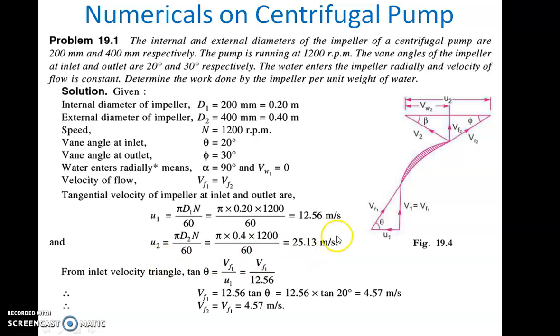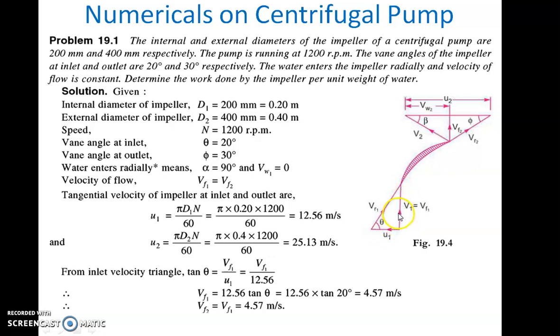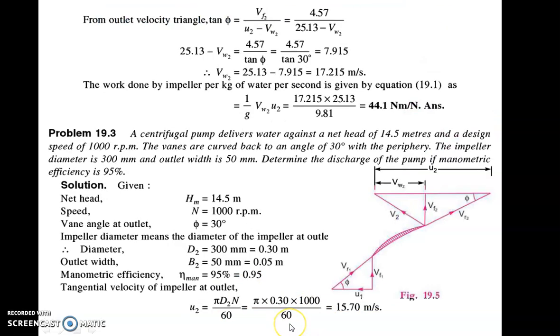From the inlet velocity triangle, U1 is known and theta is known. So tan(theta) = Vf1 upon U1. Therefore Vf1 = U1 × tan(theta) = 12.56 × tan(20°) = 4.57 m/s. Since Vf1 = Vf2, we have Vf2 = 4.57 m/s as well.